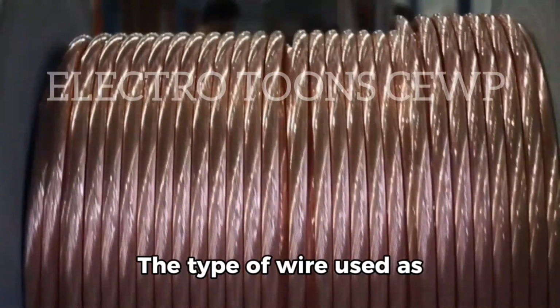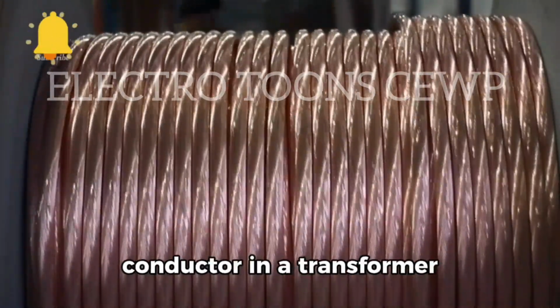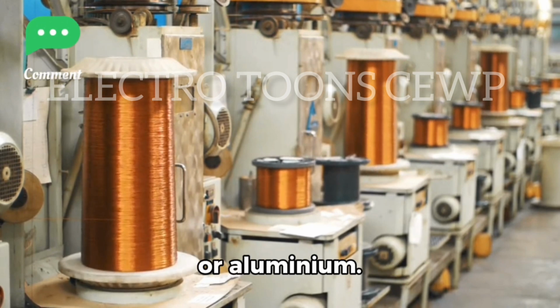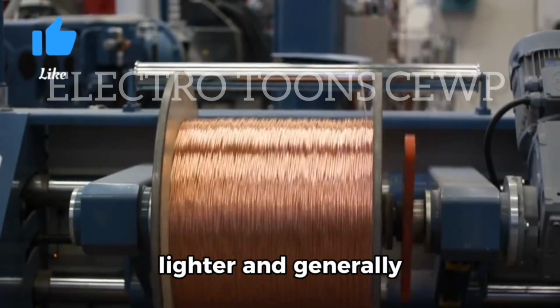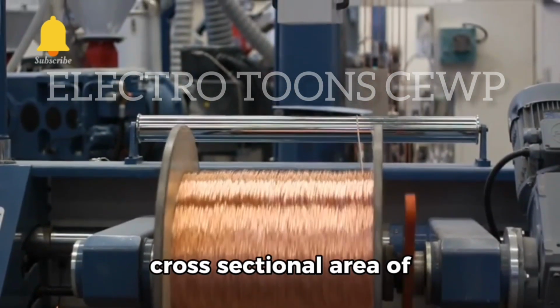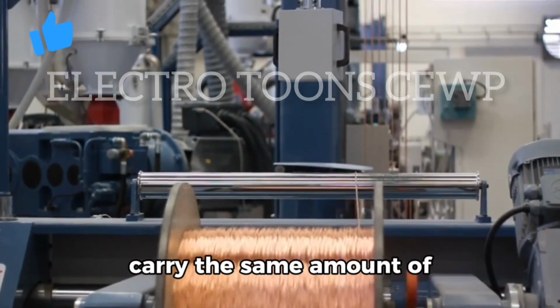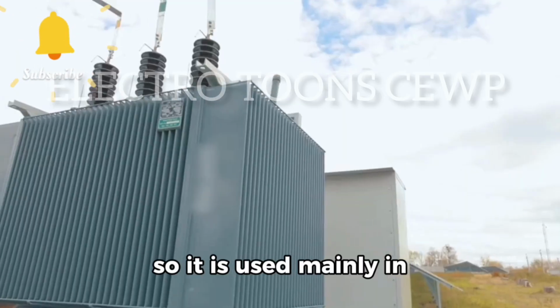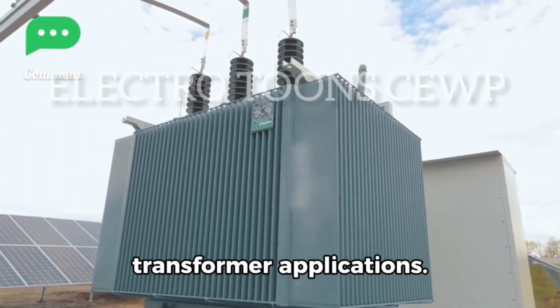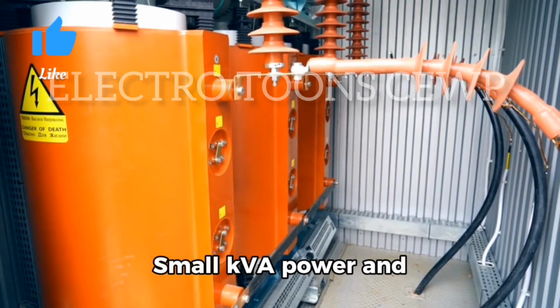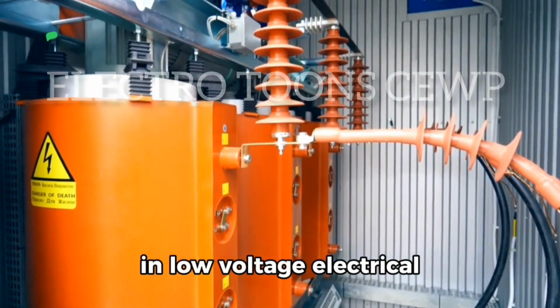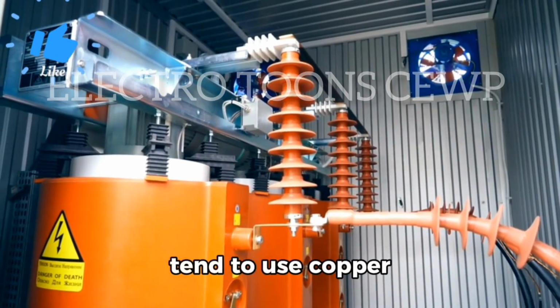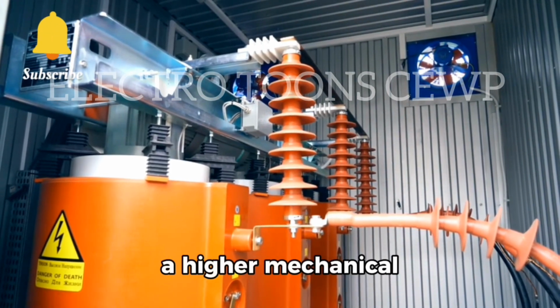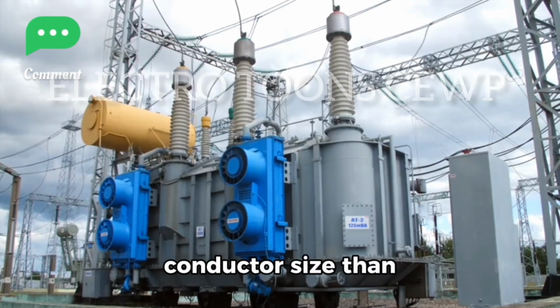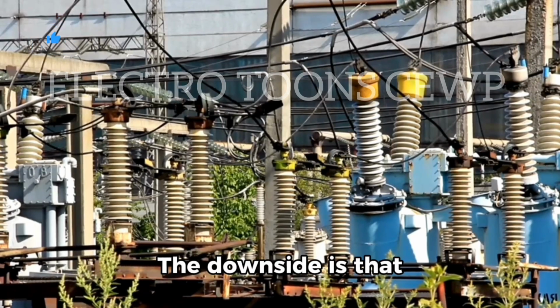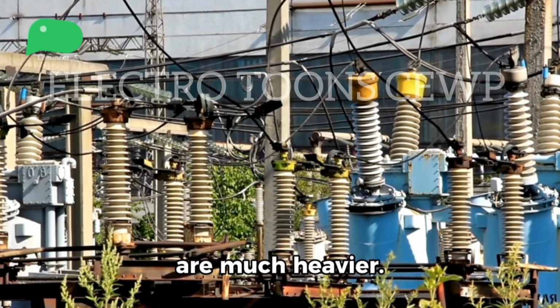The type of wire used as the main current-carrying conductor in a transformer winding is either copper or aluminium. While aluminium wire is lighter and generally less expensive than copper wire, a larger cross-sectional area of conductor must be used to carry the same amount of current as with copper. So it is used mainly in larger power transformer applications. Small kVA power and voltage transformers used in low-voltage electrical and electronic circuits tend to use copper conductors, as these have a higher mechanical strength and smaller conductor size than equivalent aluminium types. The downside is that when complete with their core, these transformers are much heavier.